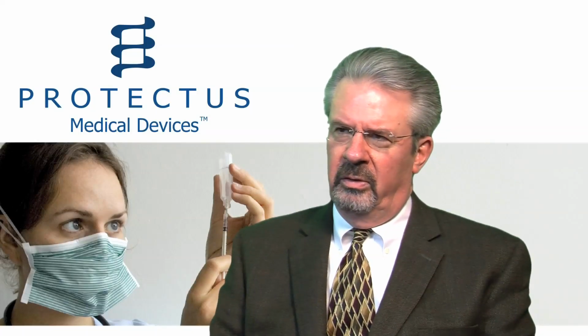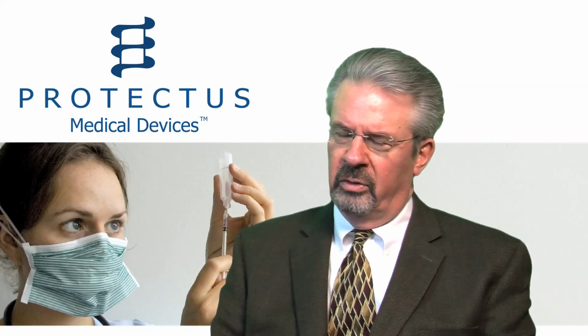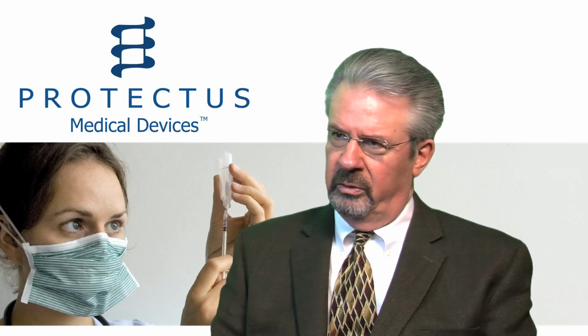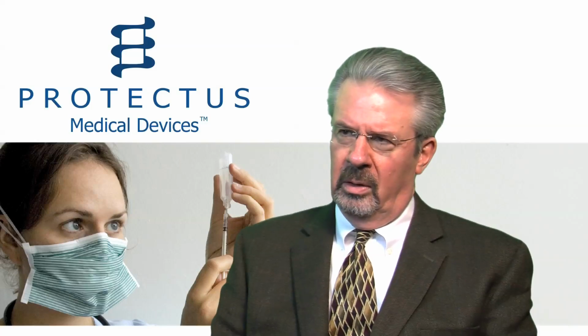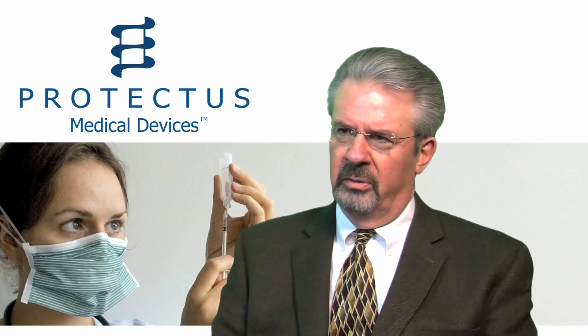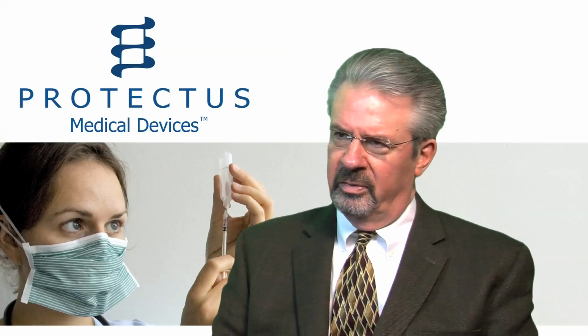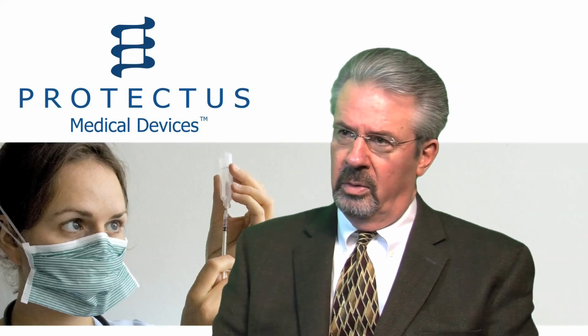The manufacturing process for the Protectus medical safety syringe is standard basic injection molding technology. We have 6 parts, and each of them is molded separately, and they are assembled using automatic assembly equipment. It is standard basic technology, it's off-the-shelf technology, so there is nothing new there.